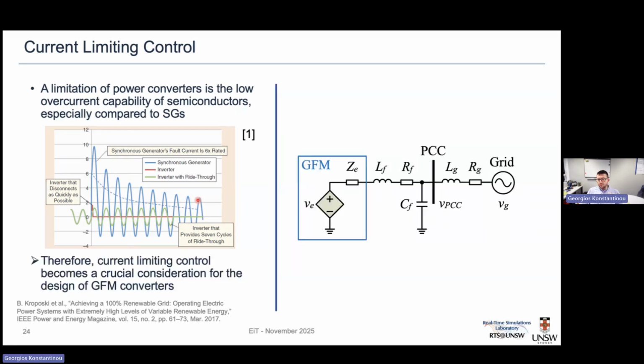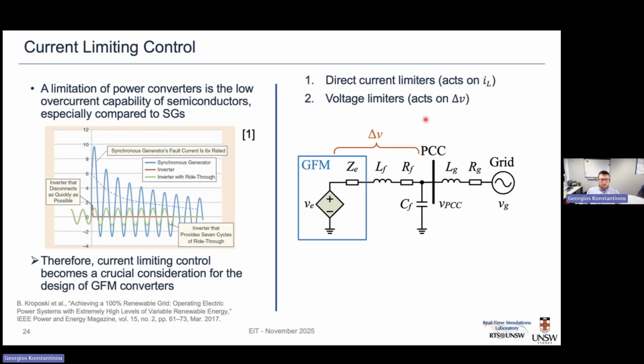So if we look at it from the point of view of power electronics control, if we are to limit this current, we have a couple of options to do that. We have what we call a direct current limiter, where we try to directly limit the current that comes out of a grid forming converter by directly affecting the control structures inside the converter. We can do it in a secondary way with what we call voltage limiters. So we are trying to limit the delta V across this value here, which includes the impedance of the converter, but also elements related to the grid and the filter of each individual converter. Or with a direct action on the overall impedance that the converter thinks it is seeing, what we call a virtual impedance, a modification of this value here at the output of the grid forming converter.